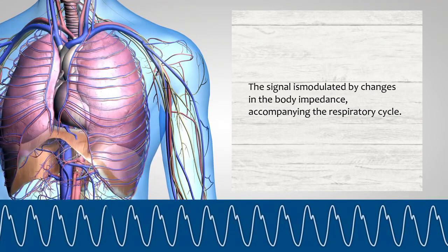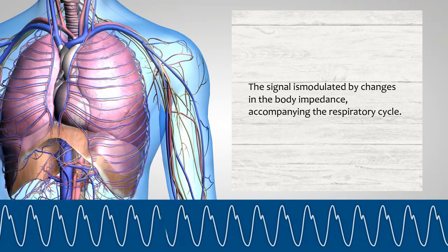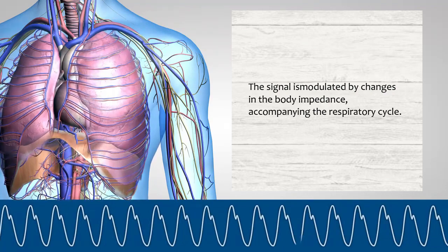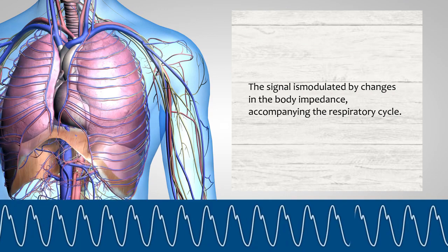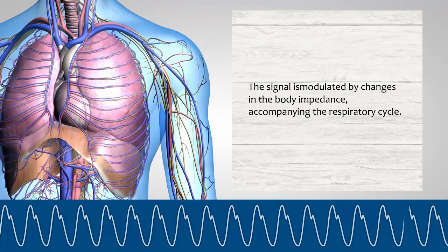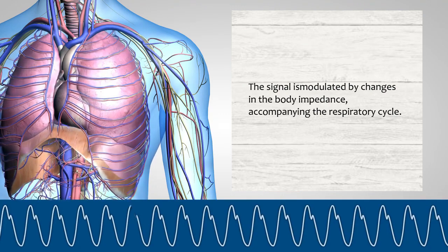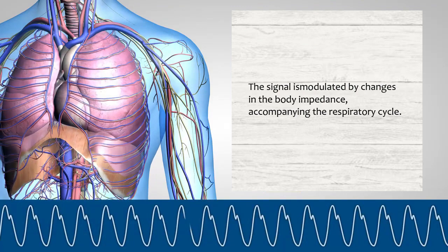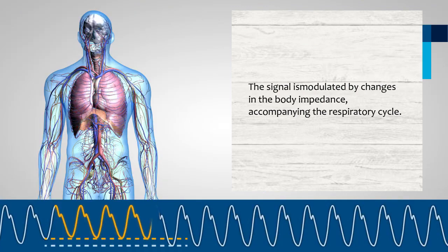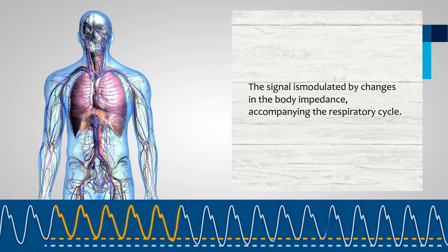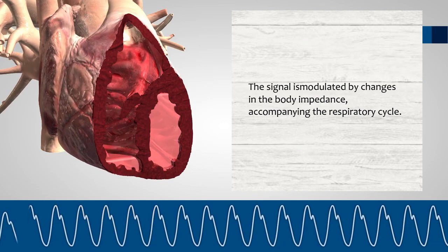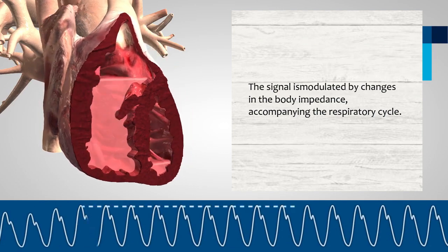The technique avoids encumbering the subject with masks, tubes, flow meters or spirometers, does not impede respiration and has minimal effect on the psychological state of the subject. The impedance method for measuring respiration rate consists in passing a high frequency current through the appropriately placed electrodes on the surface of the body, and detecting the modulated signal. The signal is modulated by changes in body impedance accompanying the respiratory cycle.